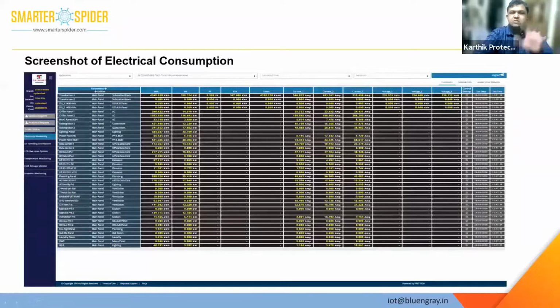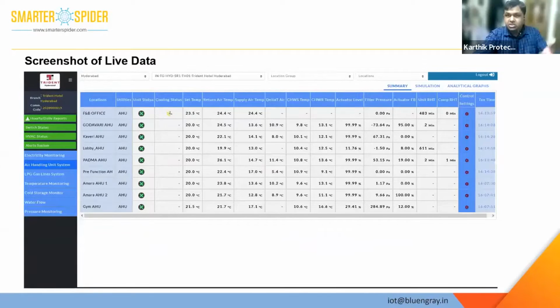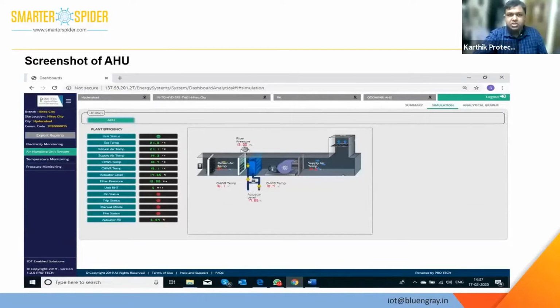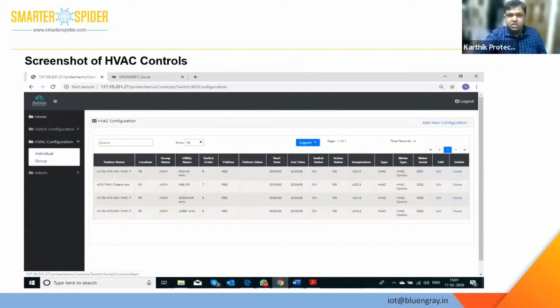This is a screenshot of some of the dashboards which we have. This is for energy meter monitoring, complete energy mapping of the facility. Then your AHU data, where we can get the set temperature, return air, supply air, delta T, chilled water supply and return, actuator level, filter pressure, feedback, etc. Then simulation of the AHU, and control settings for the AHUs.